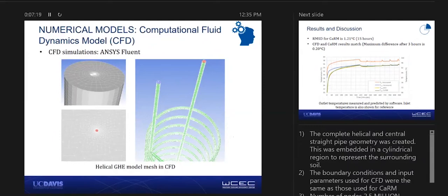Generating the mesh near the pipe interface, especially where the helical pipe starts to coil, becomes quite challenging. To keep the mesh quality good, we had to increase the number of nodes, and there are approximately 2.5 million nodes in this model. Since you're discretizing the geometry to this fine a level, the CFD model takes much longer to simulate results compared to the simplified capacitance resistance model.